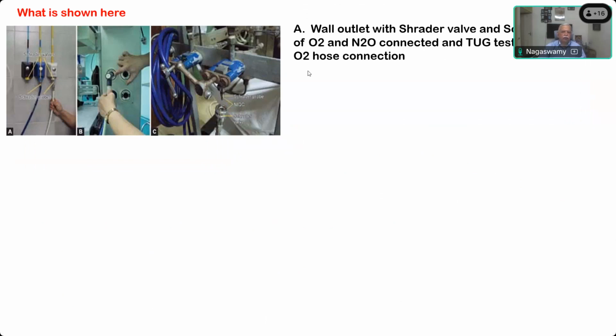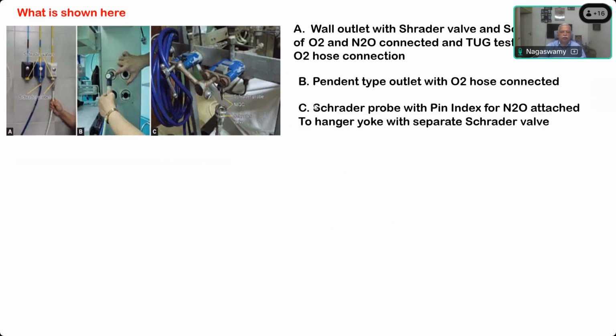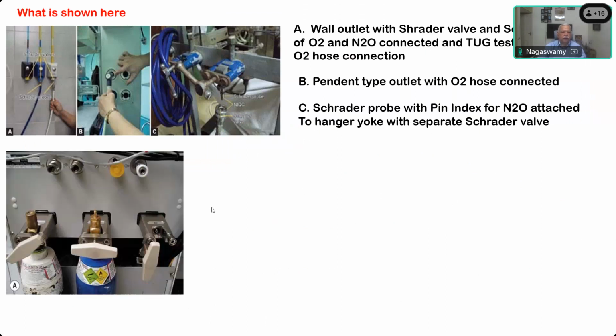being performed for the oxygen hose connection. B is a pendant type outlet with the oxygen hose being connected to that. C is a Schrader probe with pin index, for what gas we don't know because the hose color is not visible, and with a separate Schrader valve down here. So this valve can be introduced here and we can continue with the pipeline supply going to that. But in some of the other machines we have another type, as you can see here.